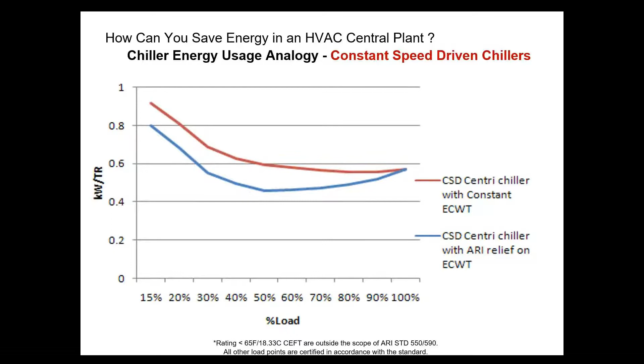So basically, as I said, here the reduction of specific power consumption is very minimal. At 100% load, both are at the same level. As you go into the part loads, there is reduction happening because you have a favorable condenser water entering temperature, which is at a lower level than your design temperature. But the reduction is not something exponential. It is not very high. The reduction is marginal. It's minimal.